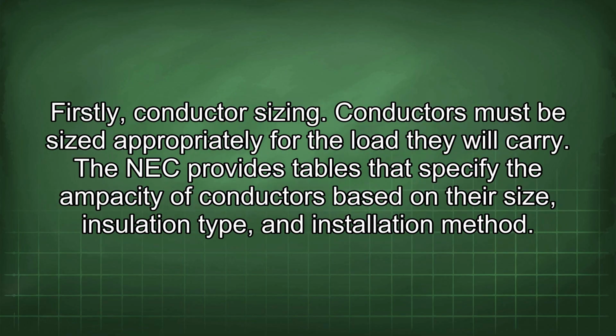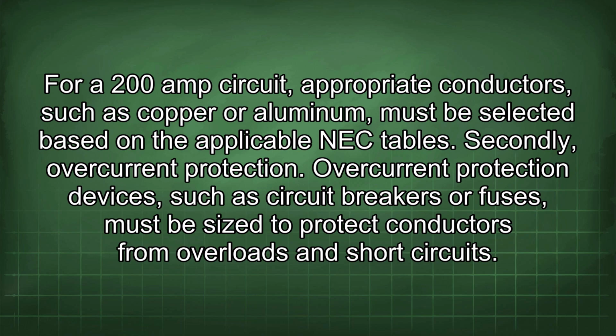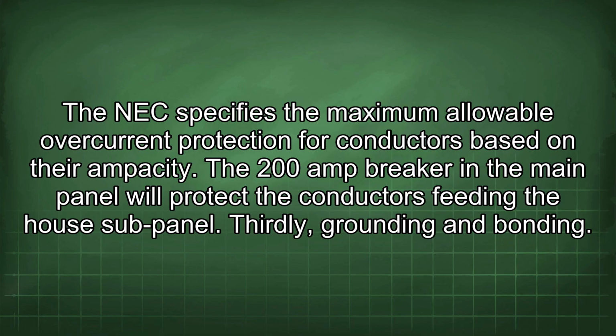Firstly, conductor sizing. Conductors must be sized appropriately for the load they will carry. The NEC provides tables that specify the ampacity of conductors based on their size, insulation type, and installation method. For a 200 amp circuit, appropriate conductors, such as copper or aluminum, must be selected based on the applicable NEC tables. Secondly, overcurrent protection. Overcurrent protection devices, such as circuit breakers or fuses, must be sized to protect conductors from overloads and short circuits. The NEC specifies the maximum allowable overcurrent protection for conductors based on their ampacity. The 200 amp breaker in the main panel will protect the conductors feeding the house sub-panel.